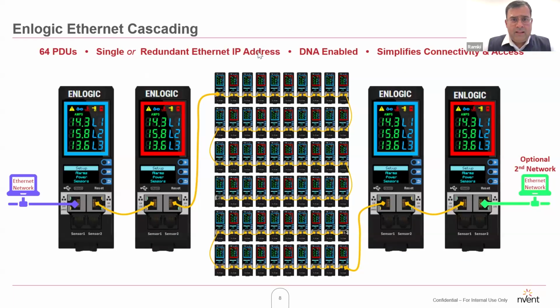Going forward, I briefly explained the two Ethernet ports available on the PDU itself. This has two functions: you can cascade, or daisy chain, up to a maximum of 64 PDUs—an industry-best specification. As you know, any network manager will tell you that assigning IP addresses is not very easy, but this allows you to configure up to 64 PDUs in a daisy chain.